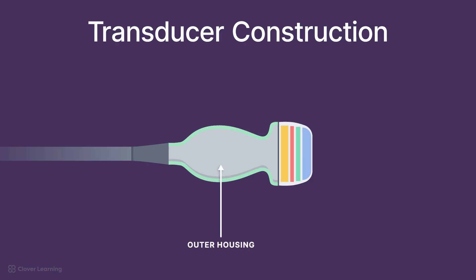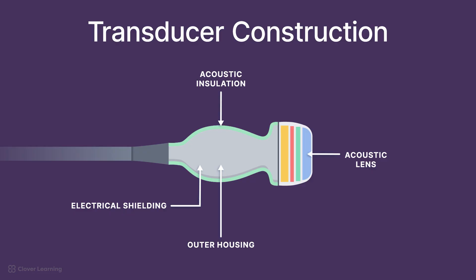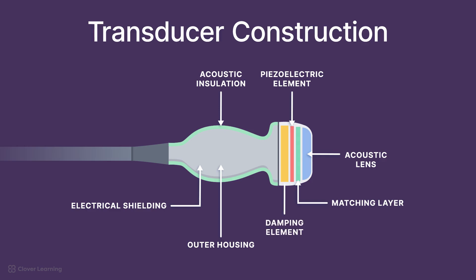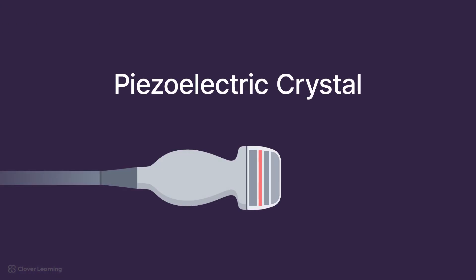The protective housing or case, the electrical shielding, the acoustic insulator, the acoustic lens, the piezoelectric element, the matching layer, and the damping element or backing layer. It's easiest to think of these components as a series of layers that each have a unique function. We'll start with the piezoelectric crystal at the center and work our way out to the transducer's protective housing.